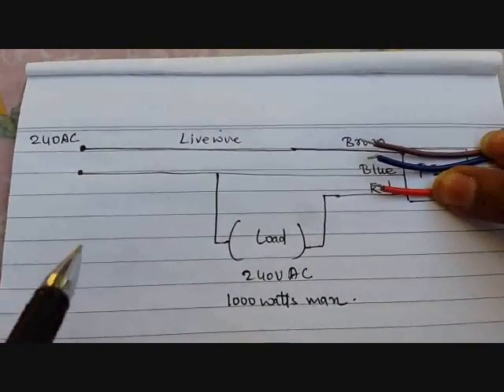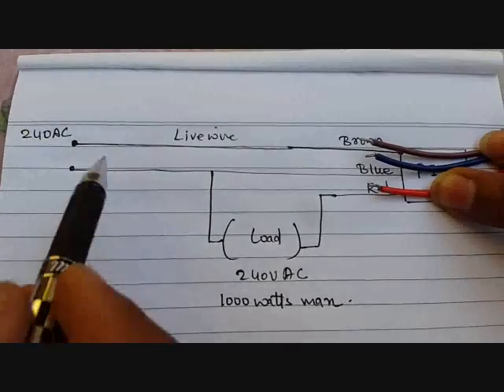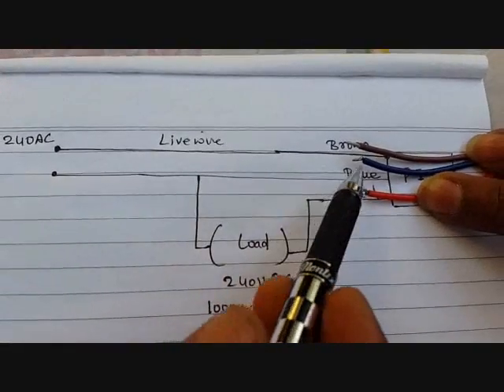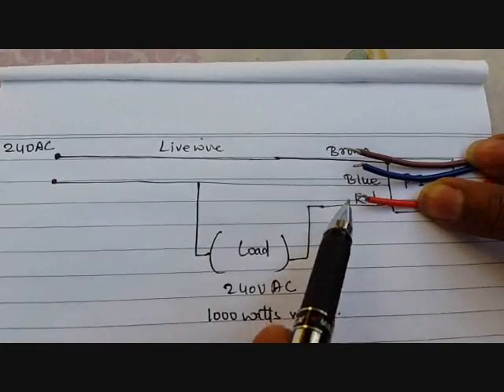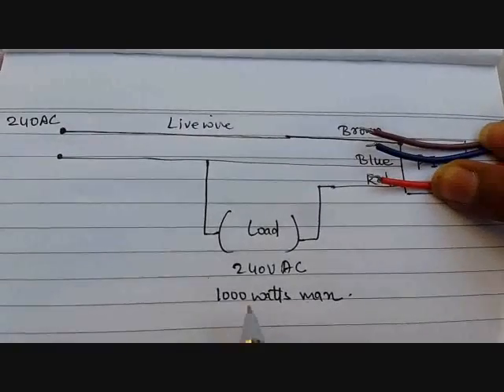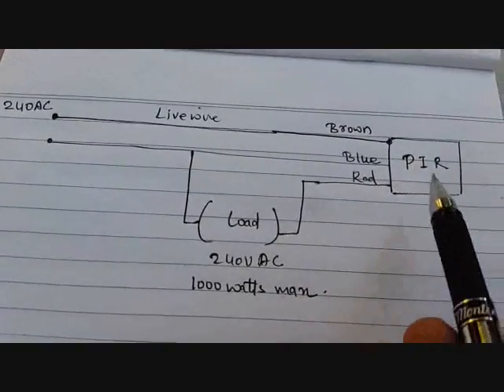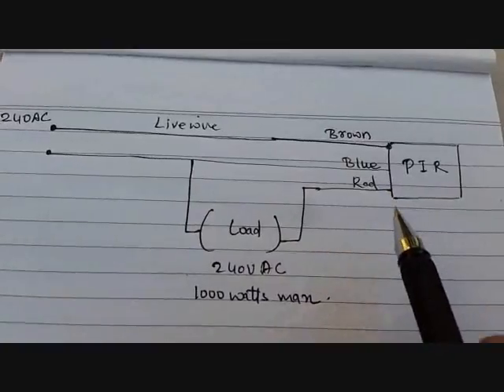This is the circuit diagram of the PIR circuit. It is connected to 240 volt AC. The live wire is connected to the brown wire of the PIR circuit. The second wire connects to the blue wire of the PIR circuit as well as the load. The third is the red wire which connects directly to the load. The load can go up to 1000 watts maximum.